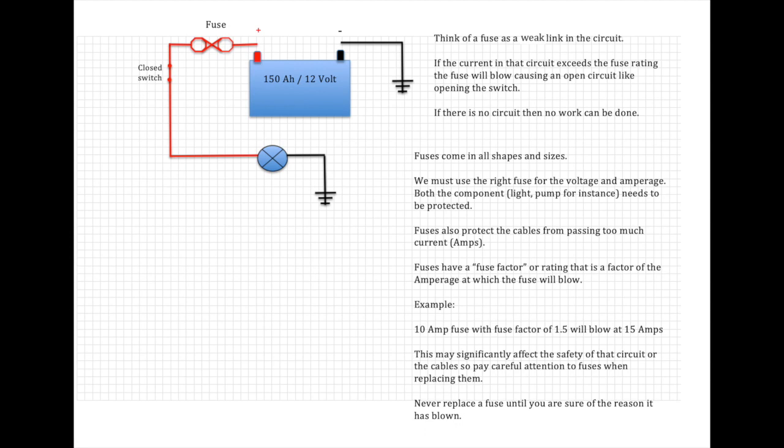Now all fuses have a fuse factor, or a rating, which is a factor of the amperage at which the fuse will blow. Here's an example. A 10 amp fuse with a fuse factor of 1.5 will actually blow at 15 amps. This may significantly affect the safety of that circuit or the cables. So be careful. Pay attention to fuses when replacing them. Make sure you have the right fusing factor.